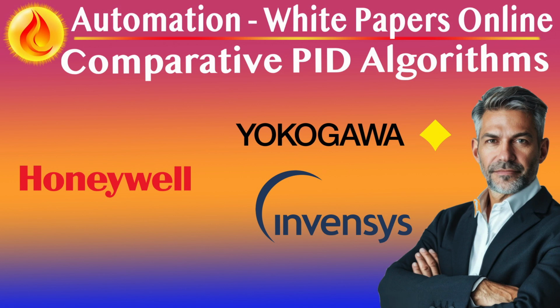Invensys, rooted in series algorithm architecture, maintains legacy compatibility with earlier pneumatic and electronic systems. The series form causes interaction between derivative and integral actions. Derivative values influence effective integral time and vice versa. This interaction introduces nonlinear behavior, requiring tuning adjustments that aren't always intuitive, especially in fast loops or during derivative activation. While modern Foxboro systems do support ideal algorithms, many plants still operate with the series default for compatibility.